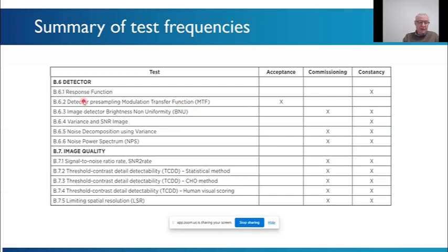For example, for the X-ray detector, the response function will vary greatly depending on the imaging mode that it's operated in and the gain, etc. The thing that will be specified maybe will be an MTF or a pixel size, which we can check quite easily. But some of the other things like the brightness uniformity or the power spectrum, they're not really specified by the manufacturer.